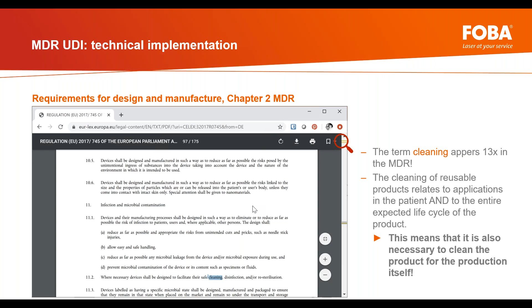It came from the FDA, but really watch out and don't say, okay, I did my finishing, I did my passivation on my retractor. After I did this and just laser mark UDI code, why should I do anything else, cleaning? You have to prove it. And I put this together here because technical cleanliness of the medical device must be proved. The corrosion resistance must be proven and documented by tests. So if you have no document, you have no test, and the other way around. So the laser contaminates the product. So the question is, and that's the right question from one auditor, how is it cleaned?